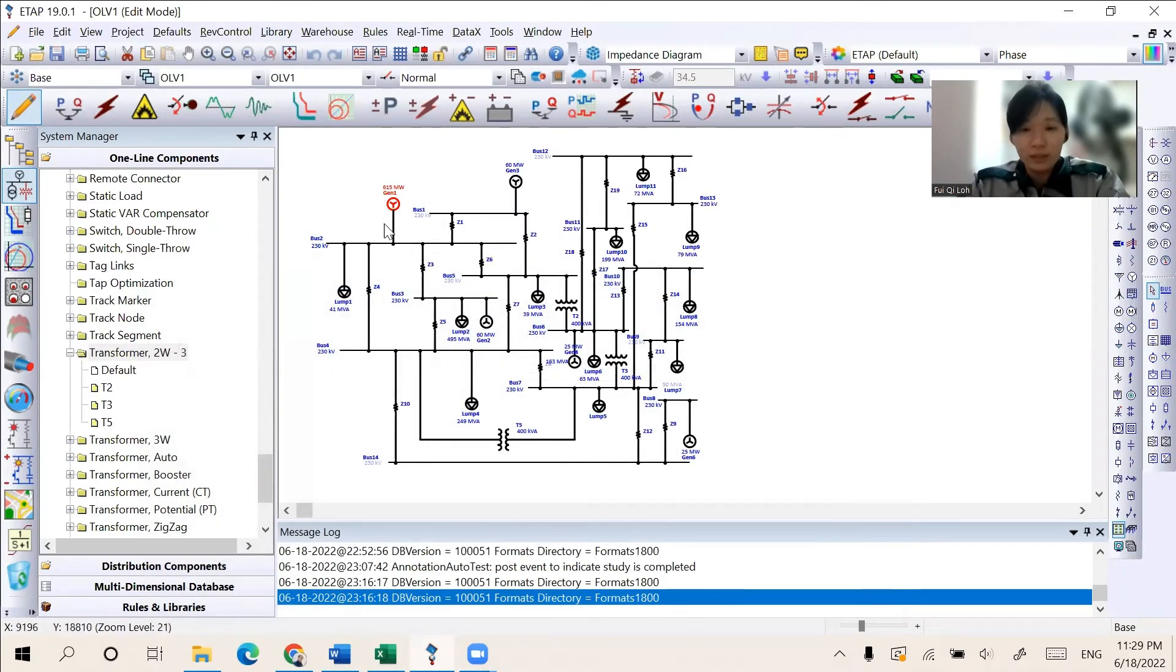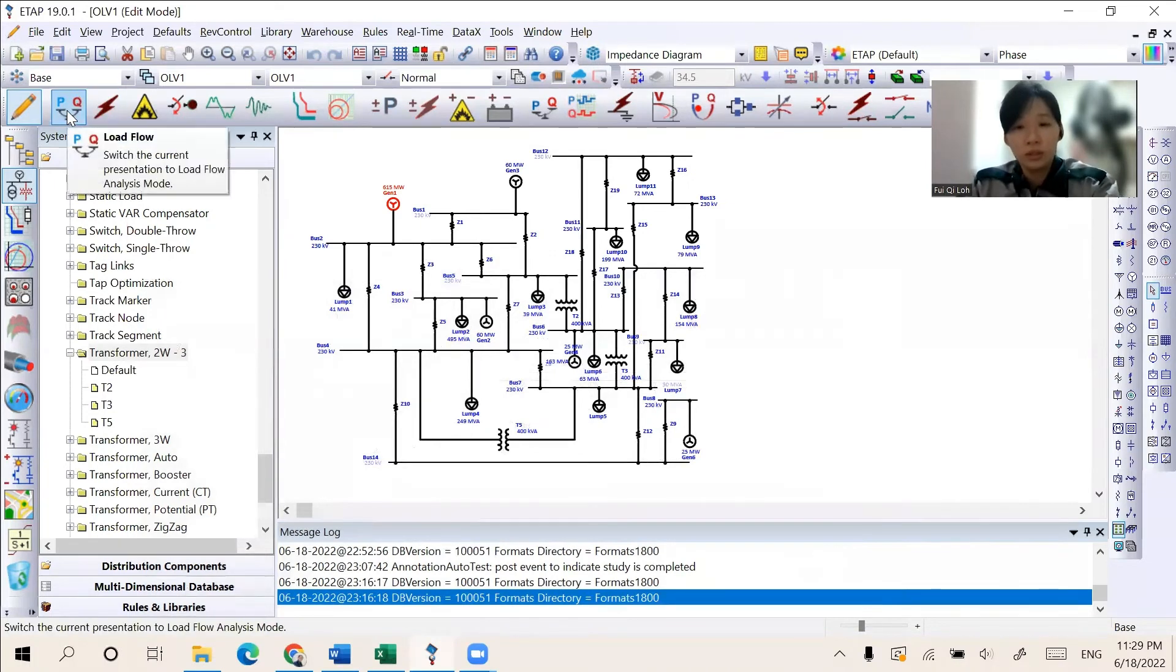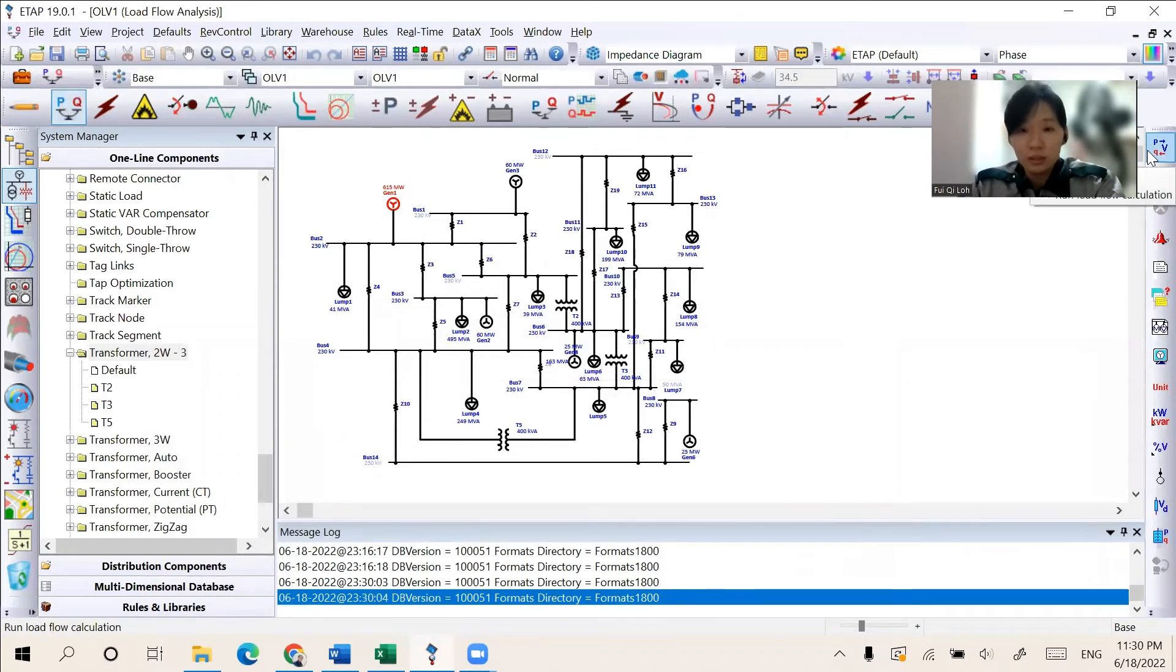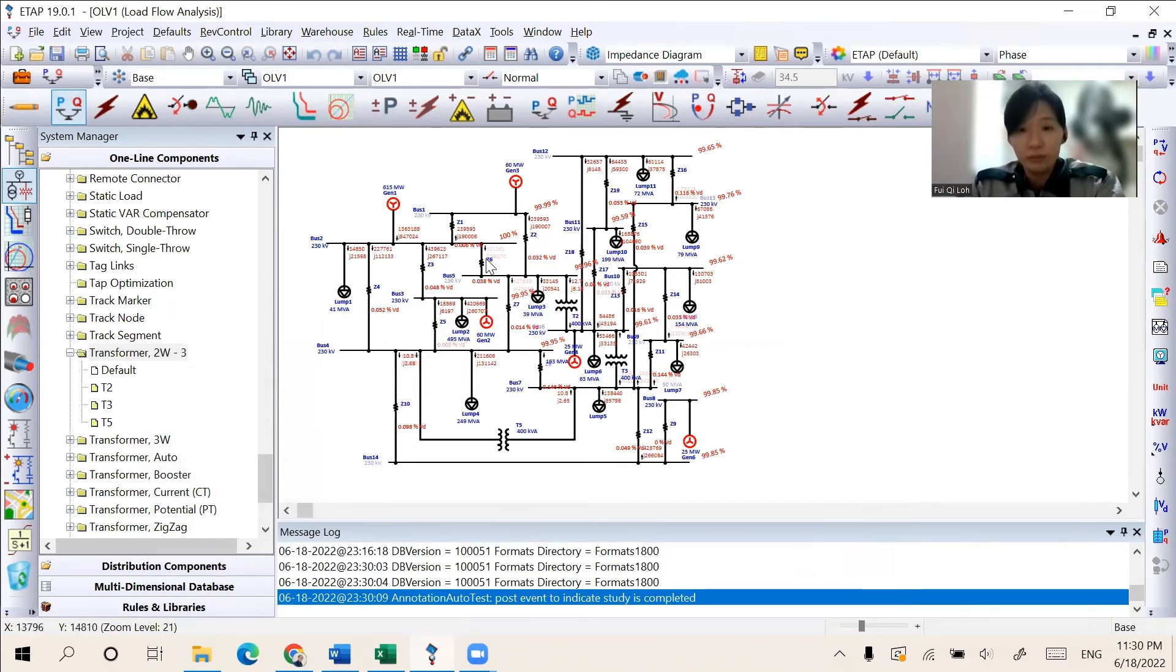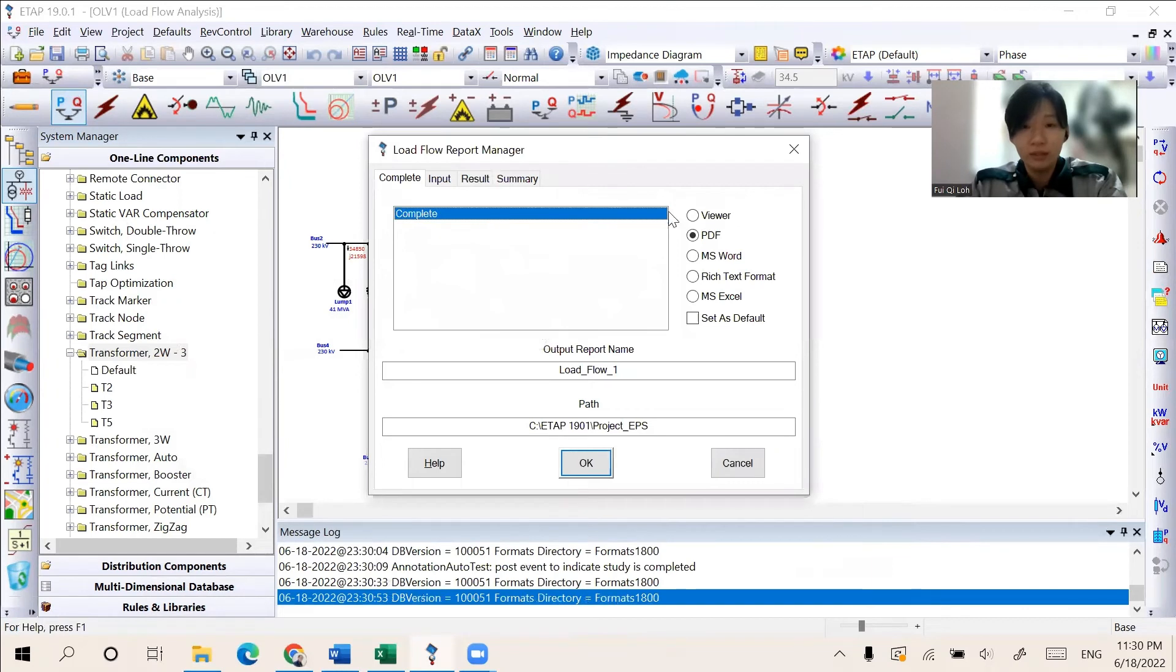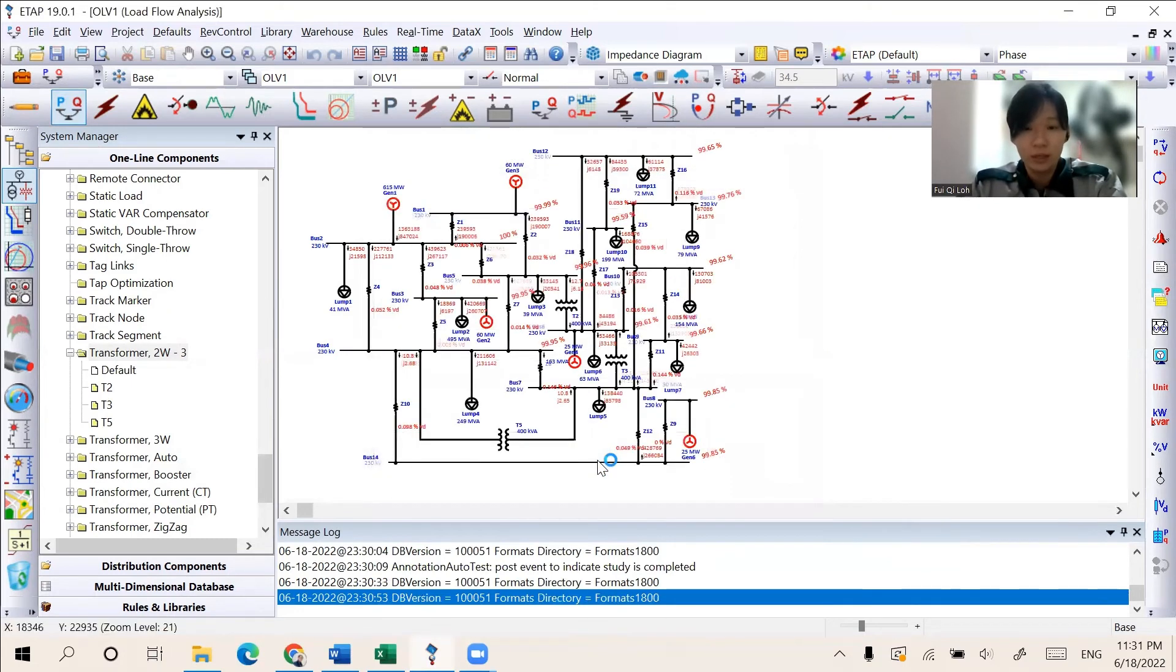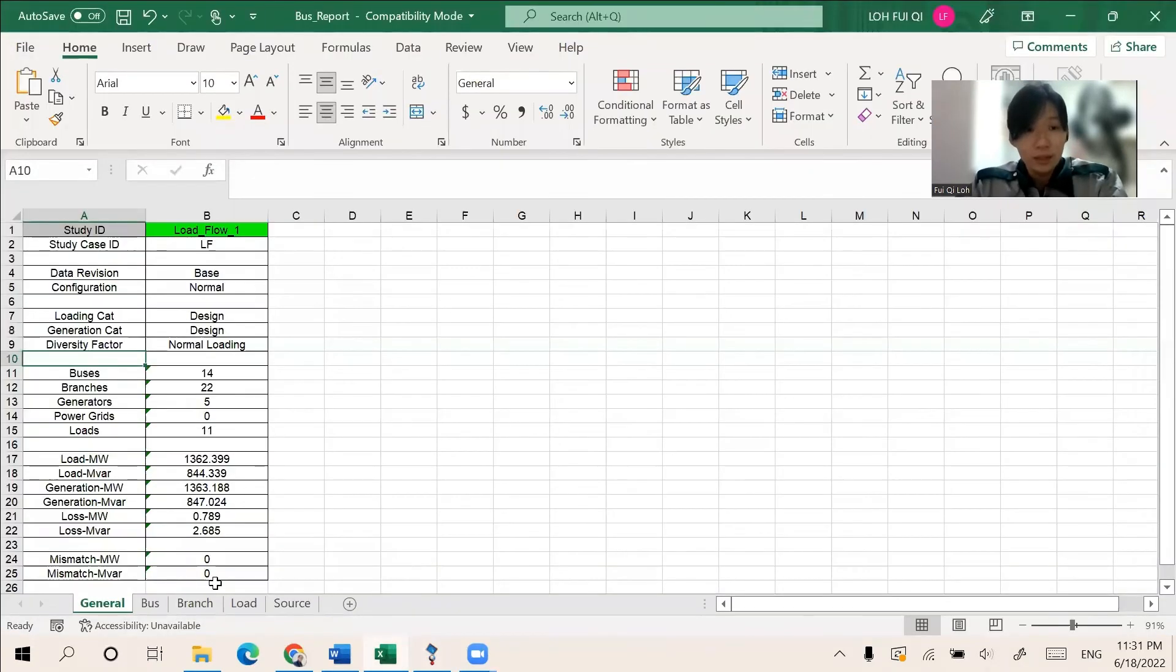After this data set is keyed into each of the components, the simulations of the load flow analysis will be run, in which we will switch to the load flow in this toolbar, and click the run load flow analysis. Then, in the main panel, we could see the rating and load flow result for each of the branches and components here. Besides that, the ETAP allows us to export the results and the analysis could be done more conveniently by the report manager here. We will select the complete result and select the format that you want. I will select the Excel and click OK, and then the report will be generated as the Excel file shown here.